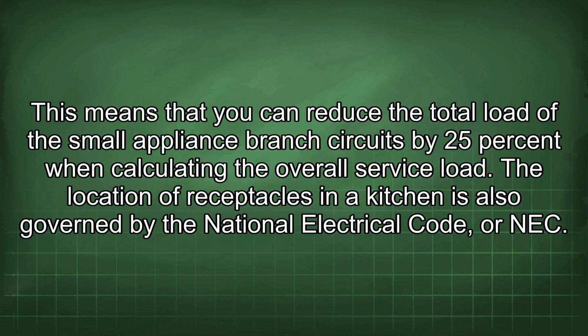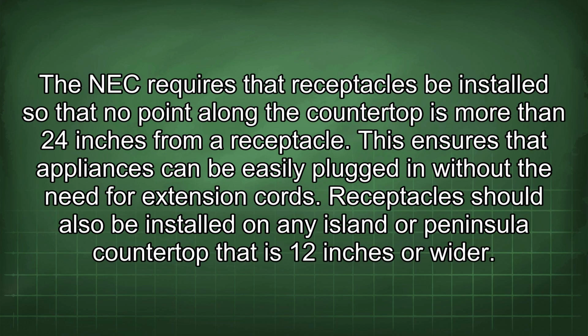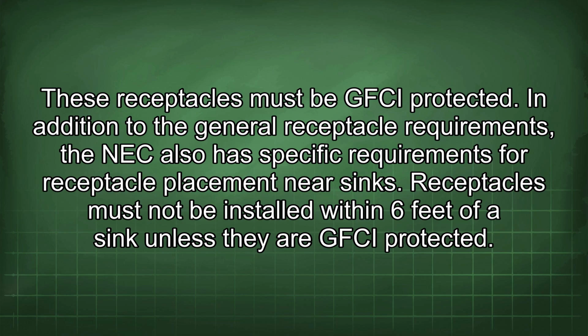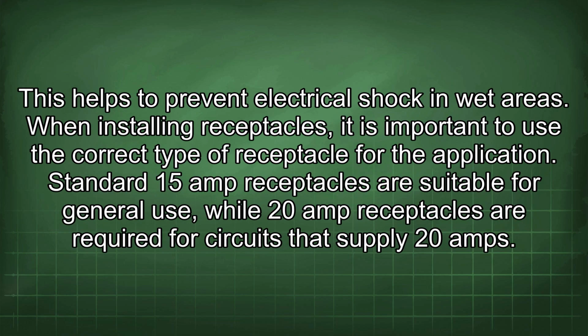overall service load. The location of receptacles in a kitchen is also governed by the National Electrical Code, or NEC. The NEC requires that receptacles be installed so that no point along the countertop is more than 24 inches from a receptacle. This ensures that appliances can be easily plugged in without the need for extension cords. Receptacles should also be installed on any island or peninsula countertop that is 12 inches or wider. These receptacles must be GFCI protected. In addition to the general receptacle requirements, the NEC also has specific requirements for receptacle placement near sinks. Receptacles must not be installed within 6 feet of a sink unless they are GFCI protected. This helps to prevent electrical shock in wet areas.